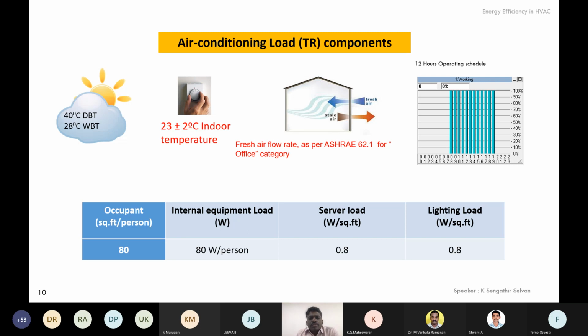Now coming to room temperature - the requirement varies from one industry to another. In a thermal plant, we have air conditioning mainly for electrical rooms, dry rooms, or control rooms. People tend to assume that a lower temperature improves the durability or life of the system, but that is not the case. We have to find optimal room temperatures - for an electrical room or control room, 25 to 26 degrees is sufficient, and for an office space, 24 degrees is sufficient.